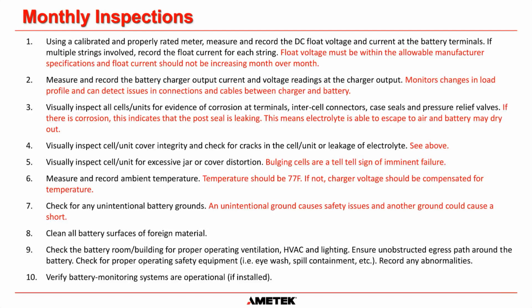Those valves on a VRLA are recombining the water back into the battery. So if there is a post leak, that means that water is getting out of the battery and it will eventually dry out. Okay, which is no bueno, that's how valve regulated batteries die. Because the electrolyte dries out and the plates corrode. Okay. Also visually inspect the cell unit cover for integrity and cracks. Obviously see above. If you have any cracks in the plastic around the battery, then that means electrolyte can leak out. Visually inspect the cell for excessive jar or cover distortion.